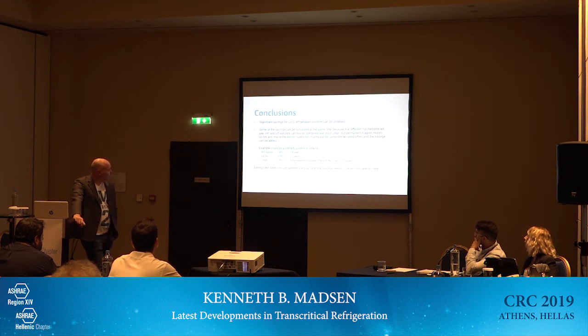Then the good thing about these savings, if we should sum up, is that there's no reason why we should not be able to run with both high pressure lift ejectors and ultra-low superheat at the same time. It's two different technologies. It's two different places we get the saving from. So here we can basically combine the savings.